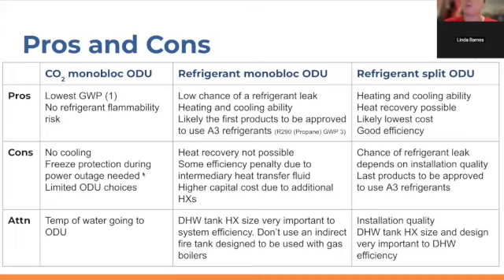They'll produce 140 degree water, 150 degree water, but for every degree that you're going higher in temperature, you pay an efficiency penalty to those higher temperatures. And so it's actually better if you can oversize your heat exchanger in your domestic hot water tank and your air handler and then be able to operate on lower temperature water produced by that heat pump in the outdoor unit. So that's true across the board. A larger heat exchanger and lower temperature water results in greater efficiency on the heating side. Same thing on the cooling side: with that larger heat exchanger size, you can have warmer temperature water, so you don't have to chill your water as cold in order to get the same amount of air conditioning power.